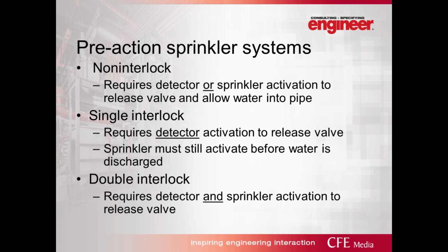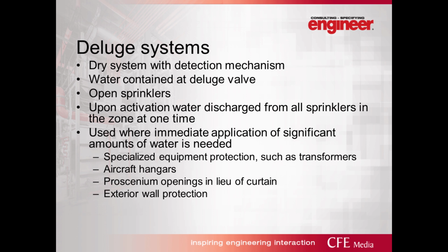And the double interlock system is the last one, and this is the one that's probably used the most often just because it provides the best protection against false alarm type things. And this requires a detector and a sprinkler to activate to release the valve and get water into the piping.